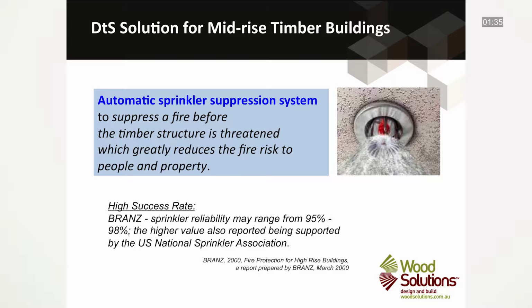Historic records and statistics over more than 100 years have shown that automatic fire sprinklers have been the most reliable fire protection system, with most estimates placing reliability above 90%. They are particularly effective because of their high reliability combined with early automatic suppression of fires without any human involvement. A study by BRANZ suggested that sprinkler reliability may range from 95 to 98%, the higher value also reported being supported by the US National Sprinkler Association.